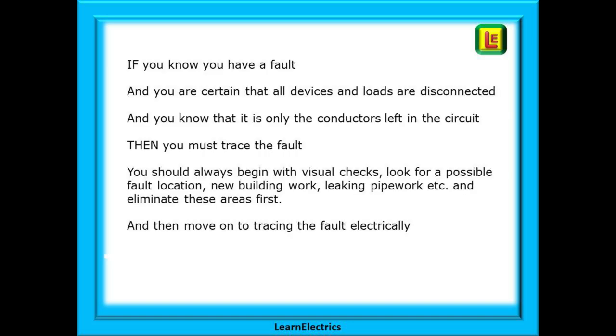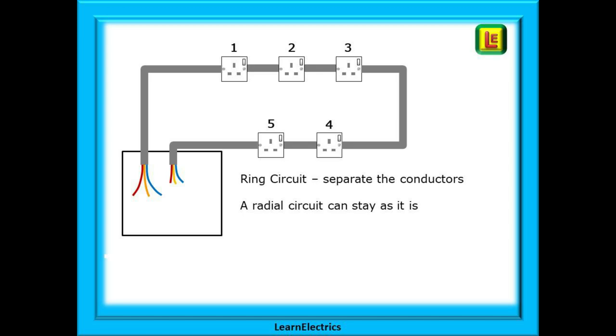But if a fault is detected, how do we go about tracing the fault behind all those walls and under the floorboards? If you know you have a fault and you are certain that all devices and loads are disconnected and only the conductors are left in the circuit, then you must trace the fault. You should always begin with visual checks — look for possible fault locations such as new building work or leaking pipework — and eliminate these areas first. Then move on to tracing the fault electrically with your test meter. When tracing faults we do not want ring circuits to be connected as a ring; we want the two ends to be physically separated, otherwise the return leg may confuse the results.